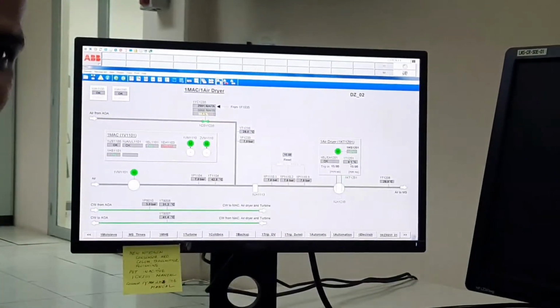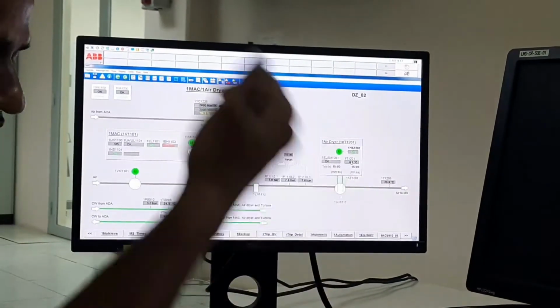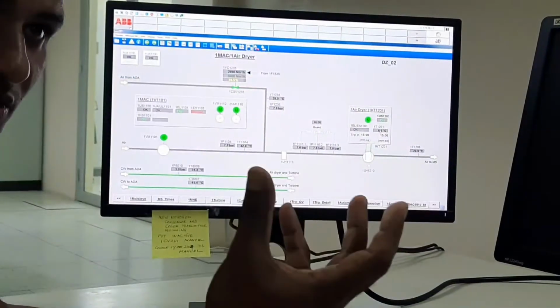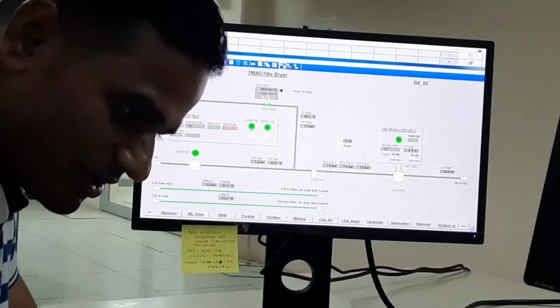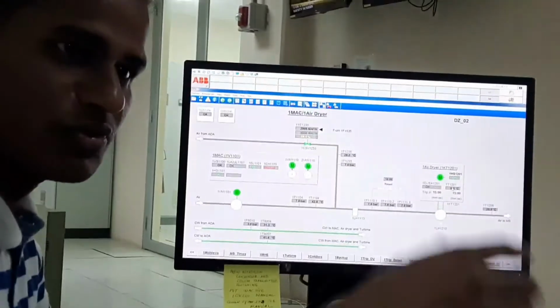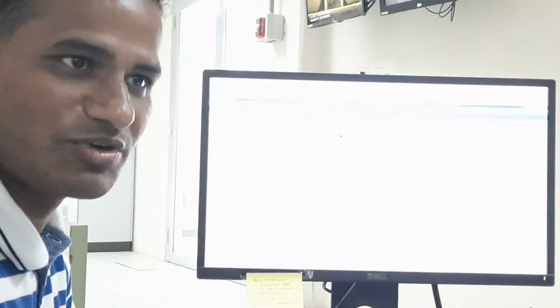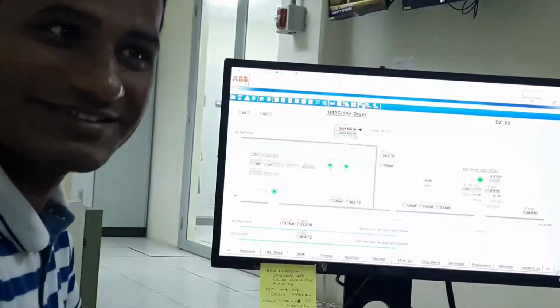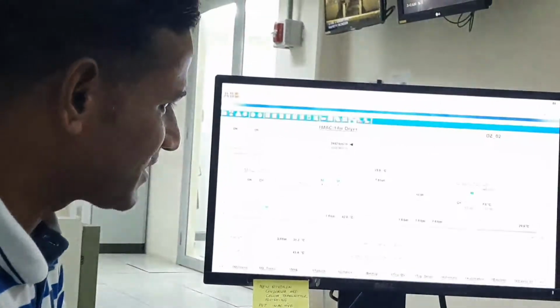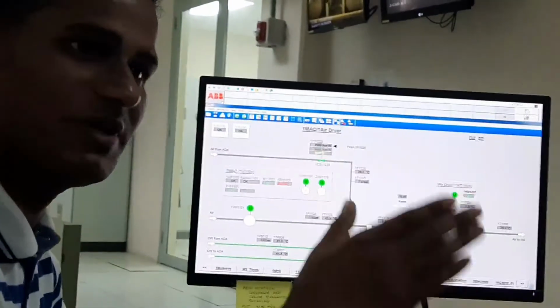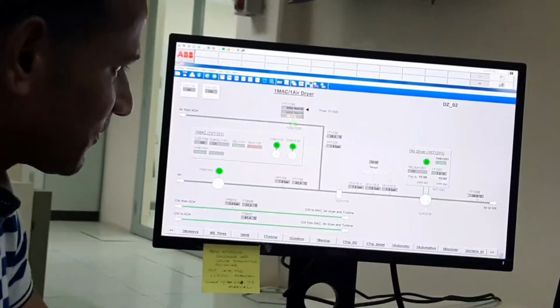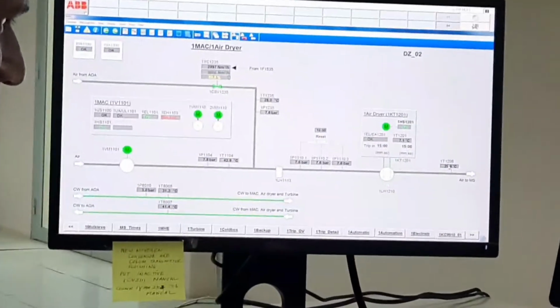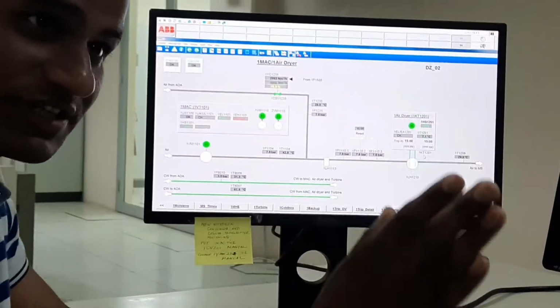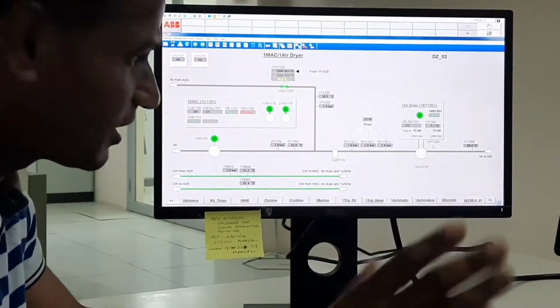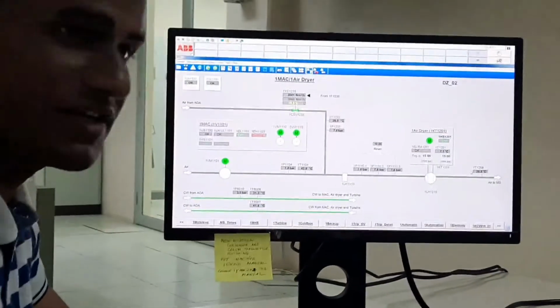On this side also there is one solenoid valve. Its main function is removing the condensate. The condensate accumulates in this trap, and this solenoid valve continuously removes it, and the air will be dry. After this, you see the temperature is still almost the same, with a small difference. So the flow is still 3,000 normal meter cube, 7.6 kg pressure and 30 degree temperature.